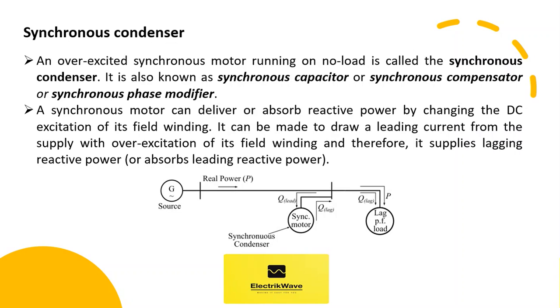An overexcited synchronous motor running on no load is called the synchronous condenser. It is also known as synchronous capacitor, synchronous compensator, or synchronous phase modifier. A synchronous motor can deliver or absorb reactive power by changing the DC excitation of its field winding.